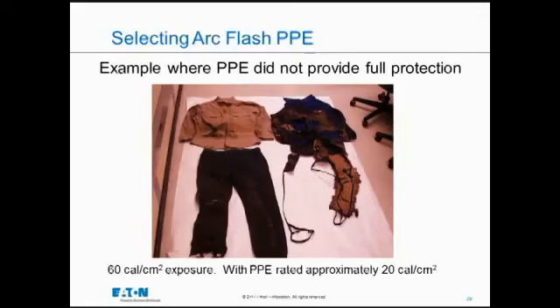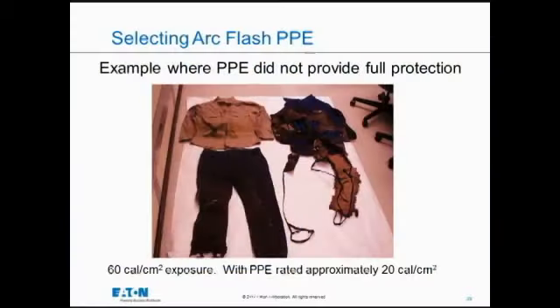This level of 2 layers of clothing was capable of about 20 calories. The exposure was 60 calories after the fact. They weren't aware it was that high, but fortunately this person received a knee burn and an ankle burn. It's not visible very well on this slide, but the clothing on the left was the inner clothing, the clothing on the right was the outer clothing, and it burnt through at the knee and the ankle. Other than that, the person came out of that one pretty unscathed.